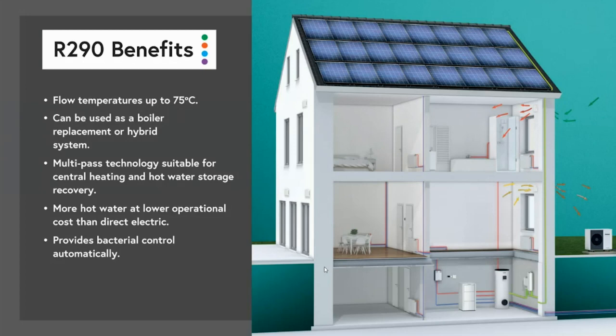And the great thing about a heat pump that can produce 75 degrees is it provides bacterial control of the cylinder automatically. So bacterial control means controlling things like Legionella, which can grow quite rapidly in water between sort of 20 and 55 degrees. So legal storage temperature in New Zealand, according to the plumbing code, is 60 degrees. So we need to be able to get the cylinder over 60 degrees, and you need a 75-degree flow temperature to be able to achieve that. What that means is the heat pump can do this without needing an electrical element at all as part of the system. Now, an electrical element can still be present, but it's not going to be used at any time for recovery of the cylinder. It's only used as a backup should there be a problem with the primary heat source.